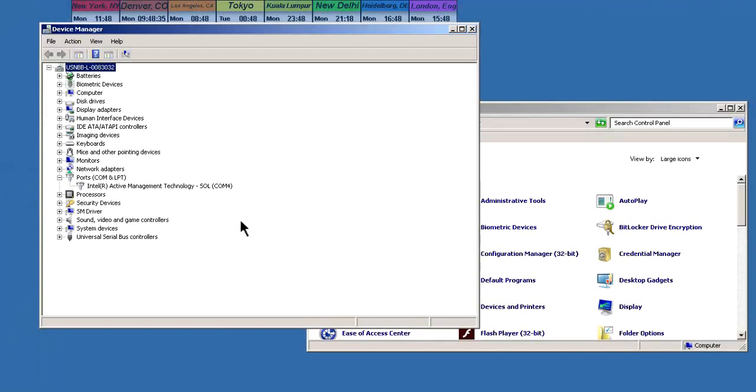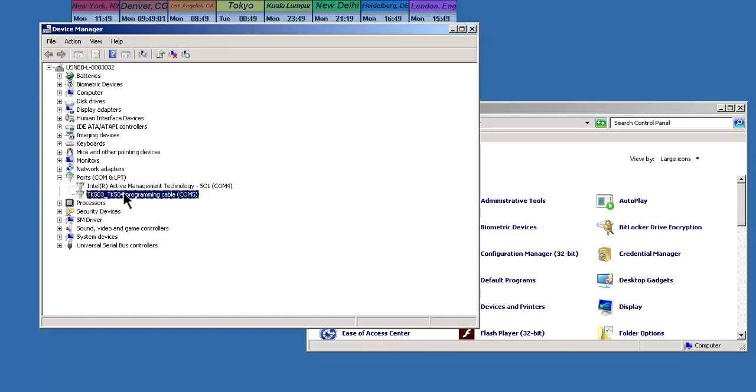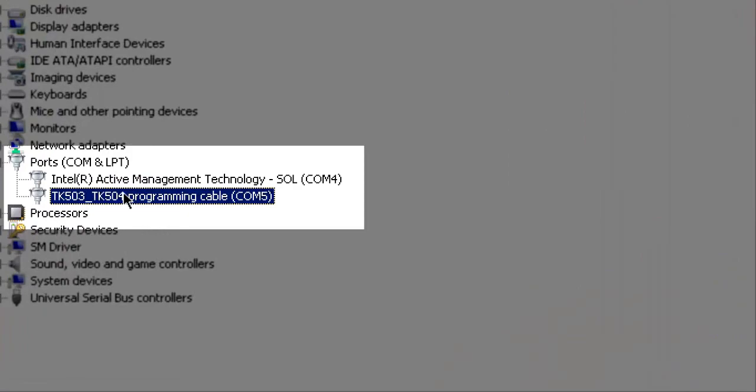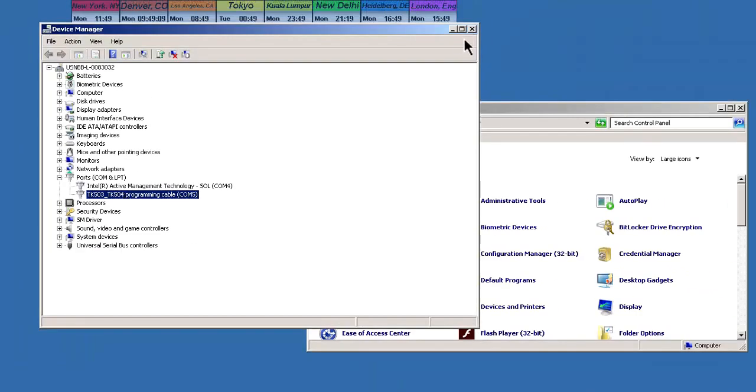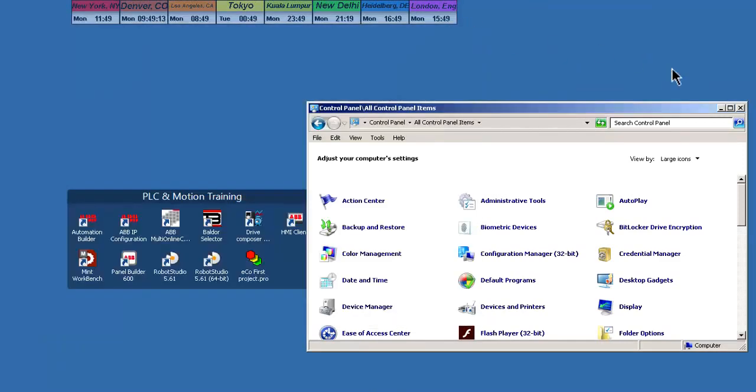I'm going to plug in one end to the serial port on the PLC and the other end to the USB port. And you'll see that Windows assigned the TK503 to the PC's COM5 port. Remember that number because that's what we have to set up in Automation Builder.